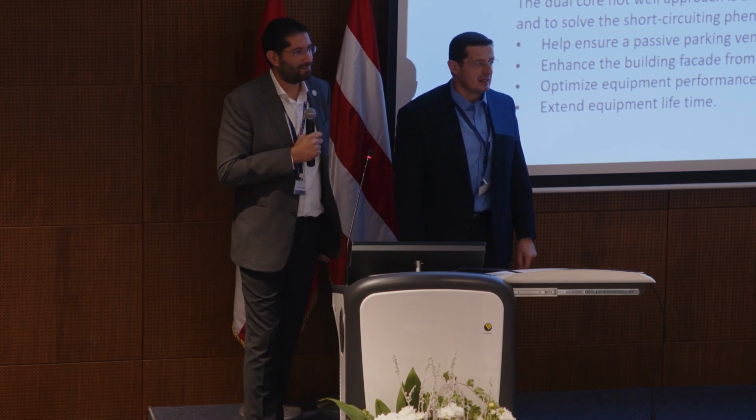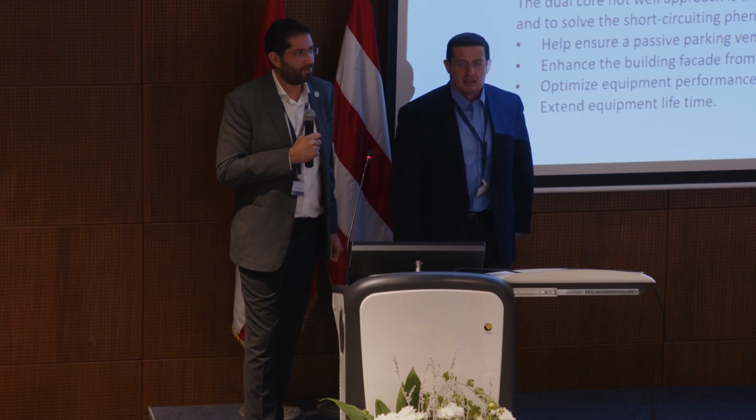Thank you for your interesting lecture. I just want to give a point about a serious matter. If a fire happens in the parking, the smoke will come at 400 degrees Celsius and will come through that hot shaft. So all the smoke will come into the flat because of the opening from the flat to the shaft for extract. This must be fire rated, because if it's not fire rated, all the smoke will come inside the flat and will create a huge problem for fire safety.